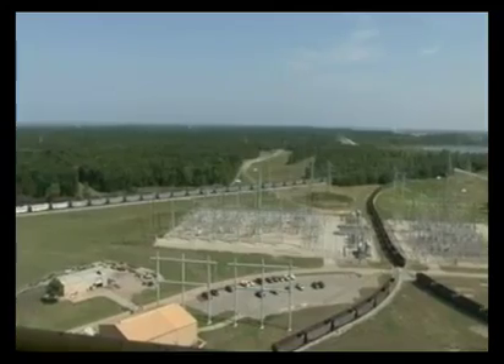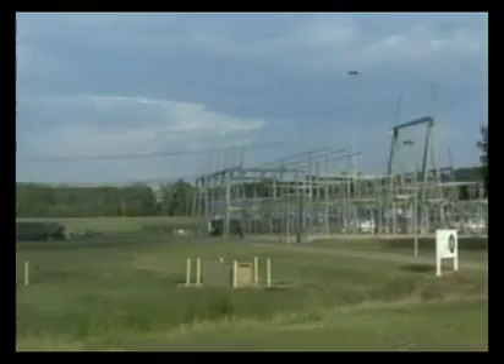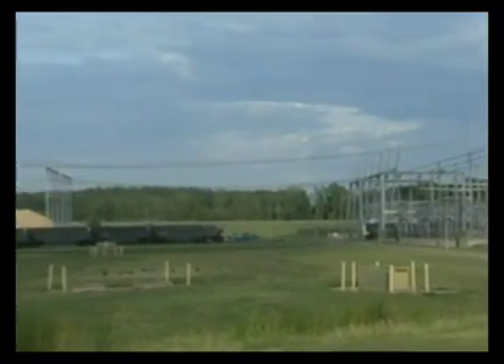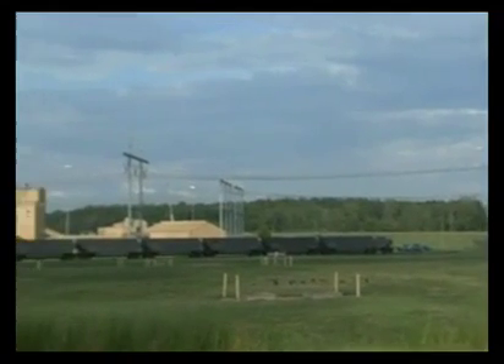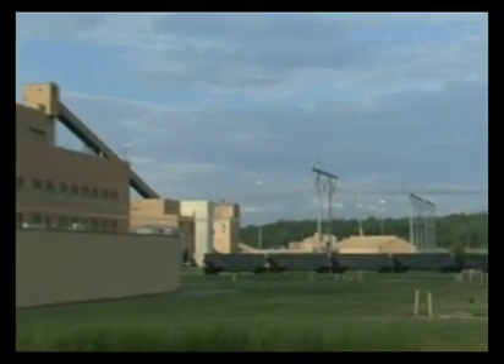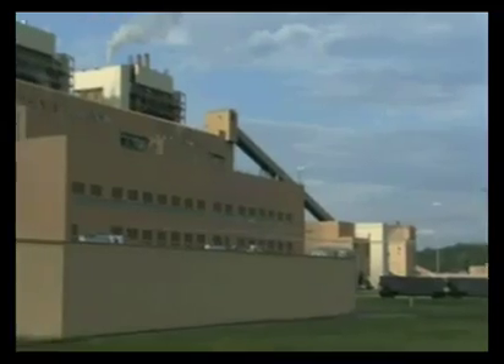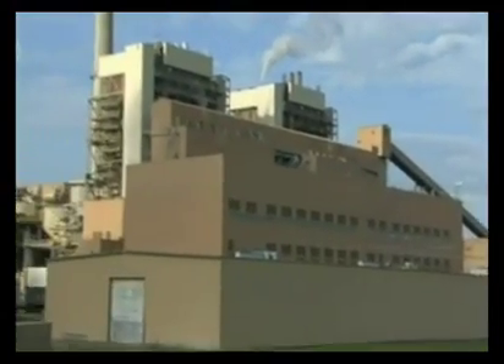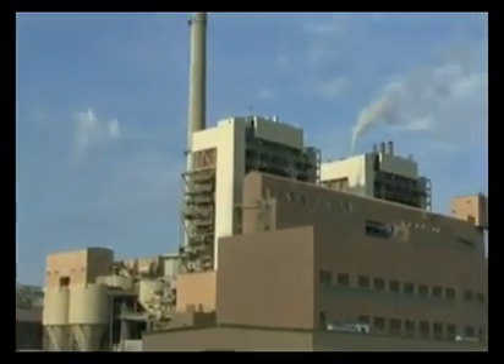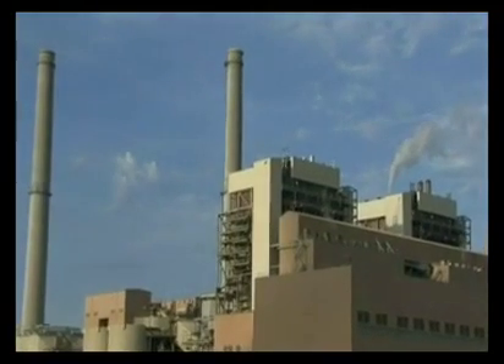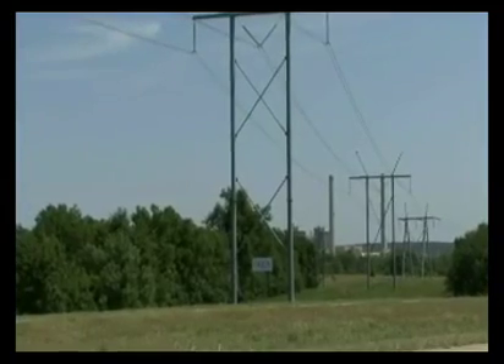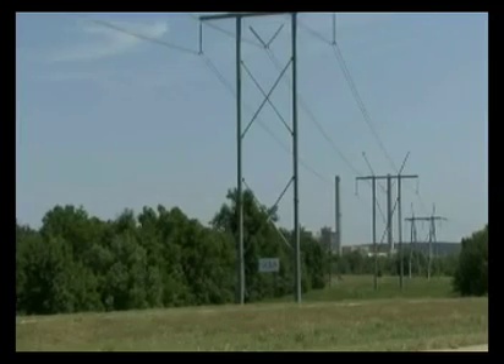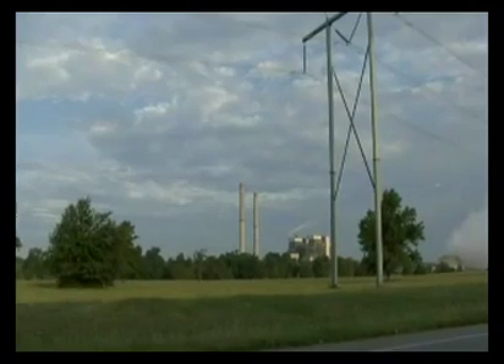Meanwhile, the 24,000 volts of electricity created within the magnetic field passes through electric transformers on the plant site and is stepped up to 345,000 volts. While that is quite a jump in voltage, it is necessary for transmission. High voltage is used for transmitting power because it reduces loss over long distances. And that's very important for GRDA because we transmit electricity across nearly 2,000 miles of lines in Oklahoma.